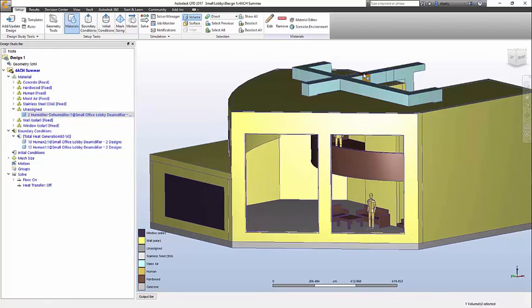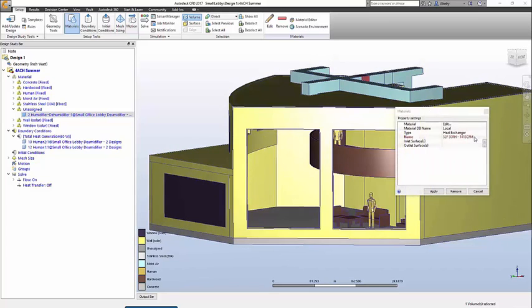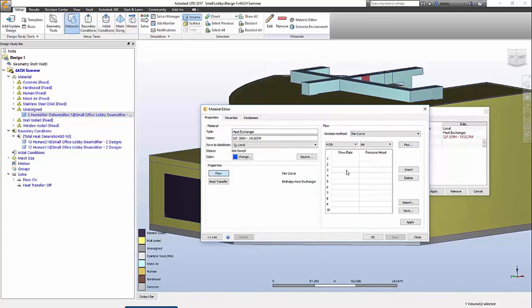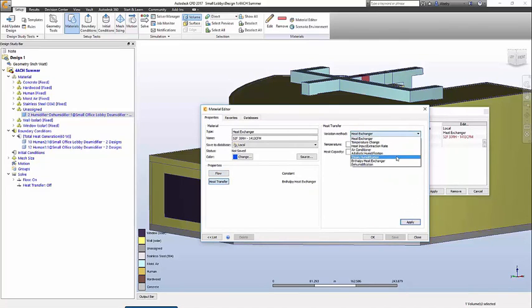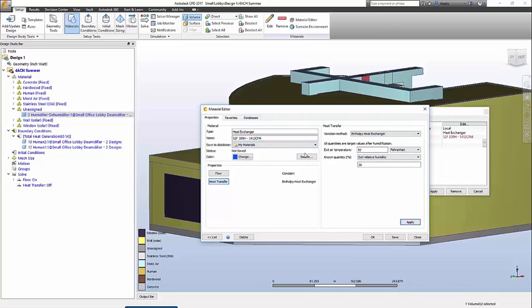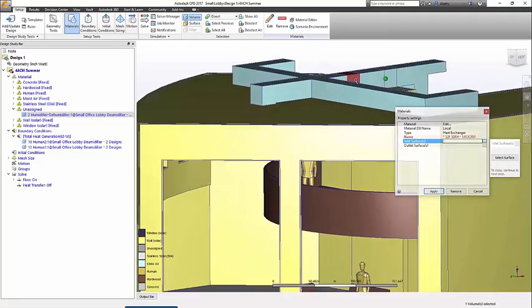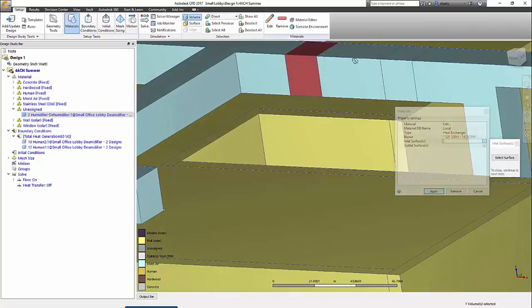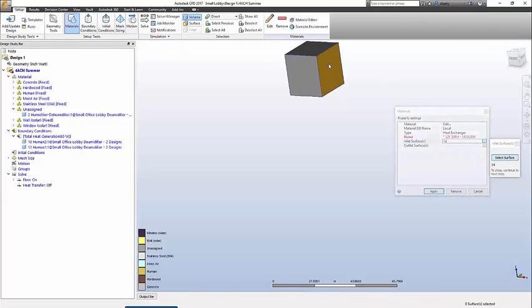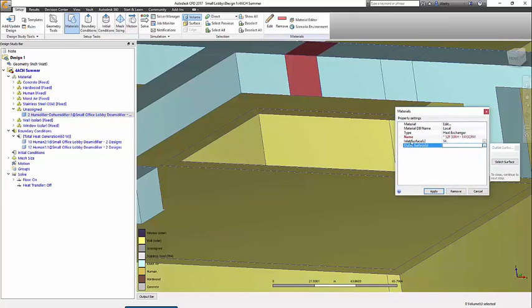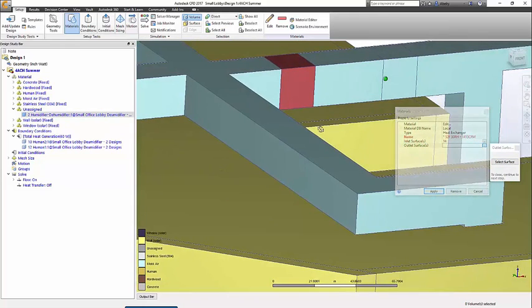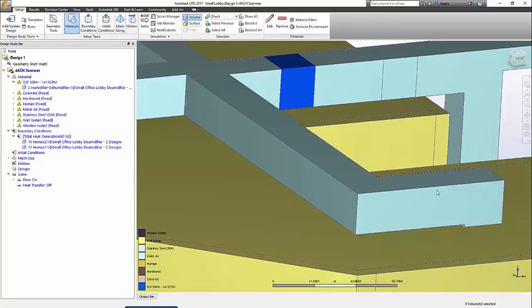This leaves one part left for setting up the model, and that is the rooftop HVAC unit. You can set up the flow rate to be fixed or varied upon a performance curve. A lot of thought has been given to the heat transfer control options, and we settled upon eight. Enthalpy Heat Exchanger is a good choice for this model because it allows you to set the exit temperature and relative humidity, which means the program will report back how much water and heat is removed, helping you size the equipment with confidence. The flow direction for the heat exchanger is defined by selecting the inlets and outlet surfaces.